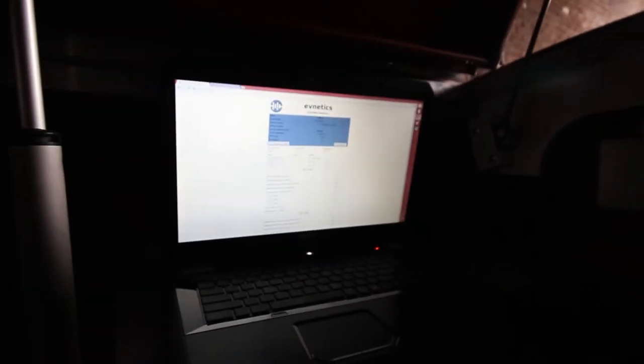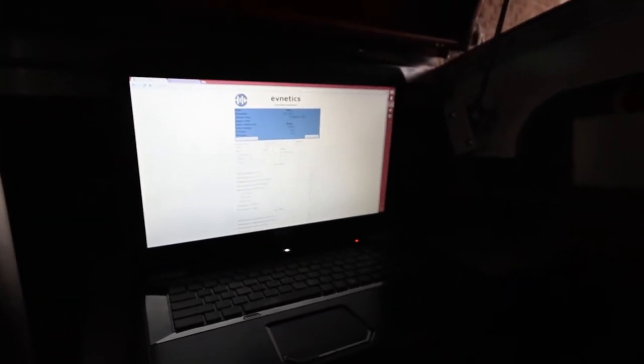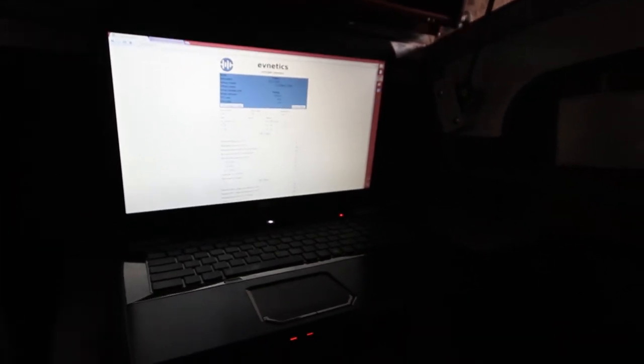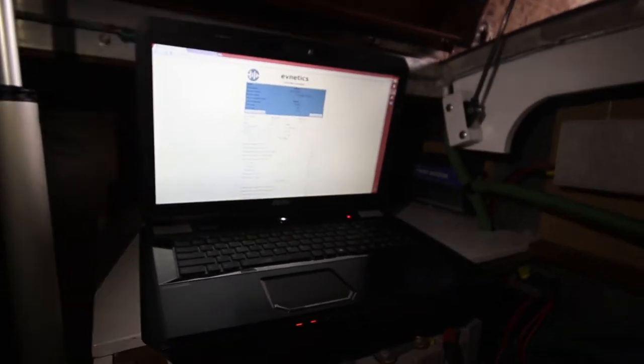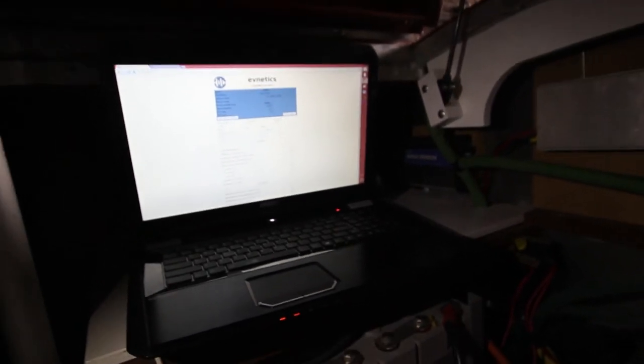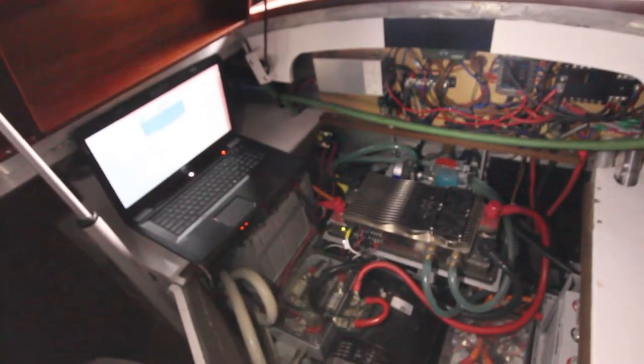Okay, we've set the idle motor speed and a maximum current for the idling. First thing that I see is I know that the minimum idle setting is 500 RPM. I wanted it a little lower, so we're gonna see if this engages a little too roughly or draws a little bit too much power. Let's check out what this does when we give it a start signal.